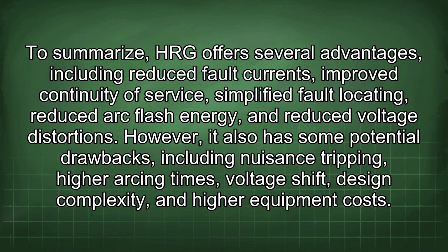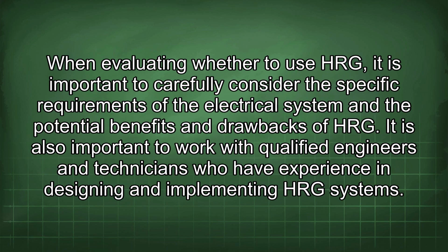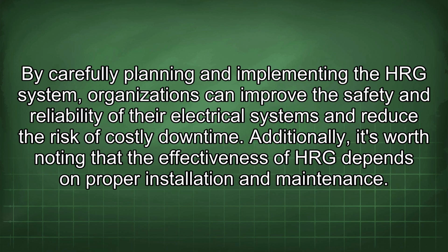To summarize, HRG offers several advantages, including reduced fault currents, improved continuity of service, simplified fault locating, reduced arc flash energy, and reduced voltage distortions. However, it also has some potential drawbacks, including nuisance tripping, higher arcing times, voltage shift, design complexity, and higher equipment costs. When evaluating whether to use HRG, it is important to carefully consider the specific requirements of the electrical system and the potential benefits and drawbacks of HRG. It is also important to work with qualified engineers and technicians who have experience in designing and implementing HRG systems. By carefully planning and implementing the HRG system, organizations can improve the safety and reliability of their electrical systems and reduce the risk of costly downtime.